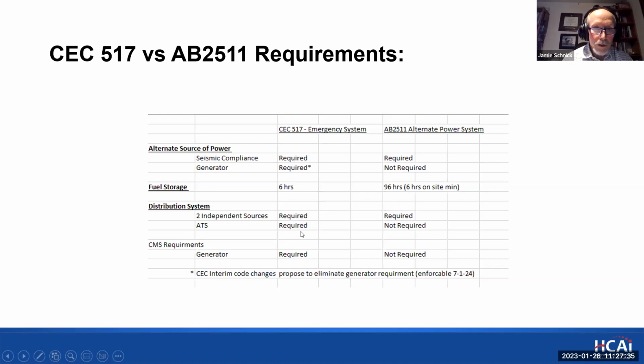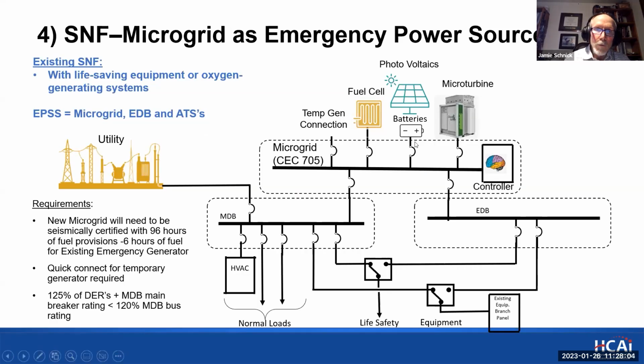Two independent sources are required, and ATS are required on the emergency side, so there's dual paths to all of your code-mandated emergency loads. Then there's the CMS piece - federal reimbursement requires that you meet CMS requirements, which on the emergency side is required, but on the alternate power side isn't. The reason I pointed this out is that the microgrid solution meeting the new bill's requirements very nearly meets all the requirements of 517.